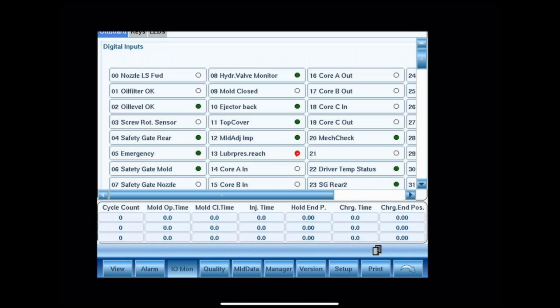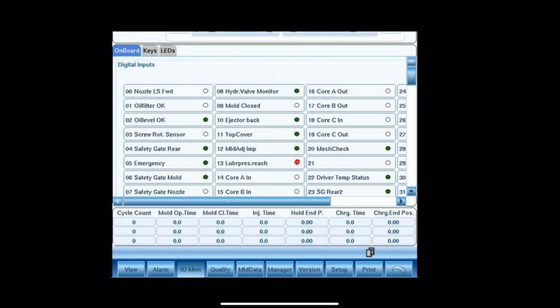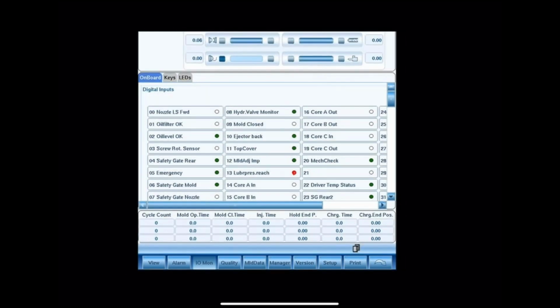And you can always force the outputs. So it's a good troubleshooting tip. If you have a problem with a valve or something, you can actually force the output, go to the valve itself and check to make sure the signal is getting to the valve. If it's not, then you can trace where the error is on the wire.